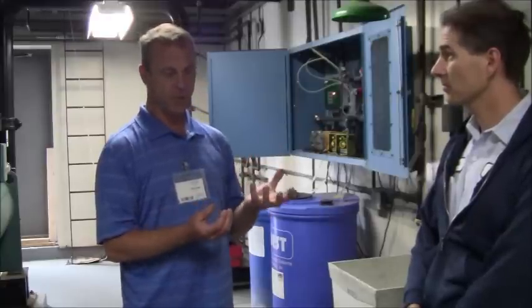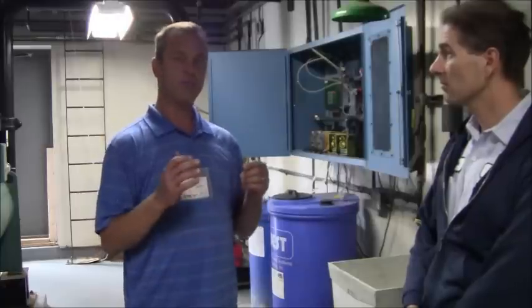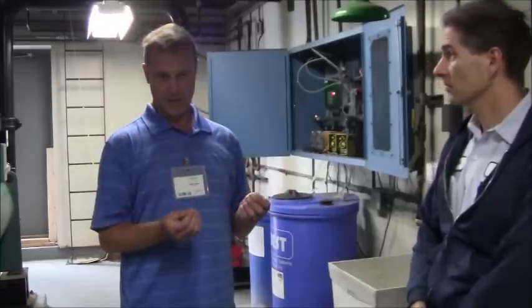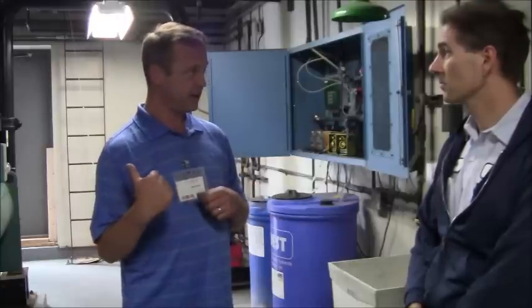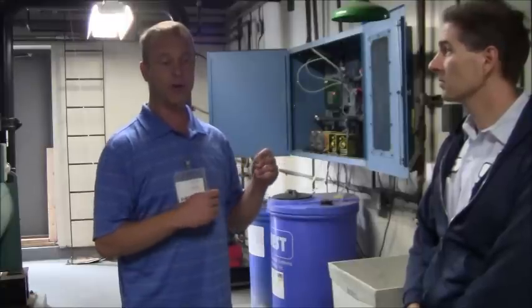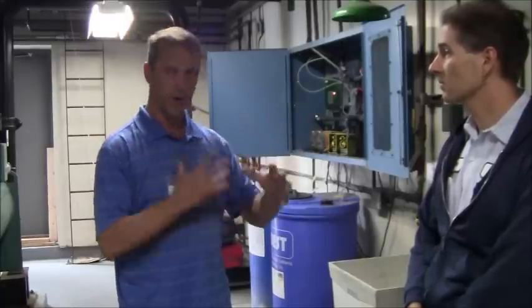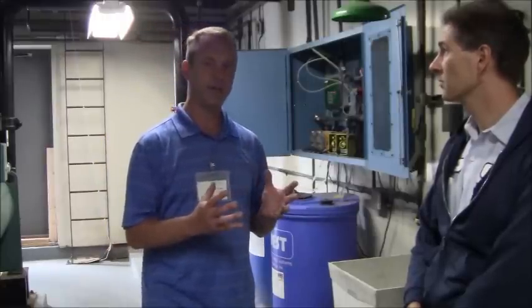You don't see them, kind of like when you pour salt into boiling water for pasta and it dissolves. We have what we call dissolved solids; people call it dissolved salts, some people call it TDS, total dissolved solids. It's basically nothing more than minerals in the water that will form scale if we don't treat it with some type of inhibitor. And since this process is evaporating water, making up fresh water, and going on all day long, what's known as conductivity builds up. Conductivity is basically a measurement that we use with testing to see how much mineral composition is in the cooling tower water. The higher that gets, we have to put a limit, a threshold, on how many minerals we have in the water. Otherwise, we will supersaturate the system and form scale, even if we have an inhibitor in there. So that's where we get to the control systems that are going to monitor the conductivity for us constantly, basically all day long as the plant's running.